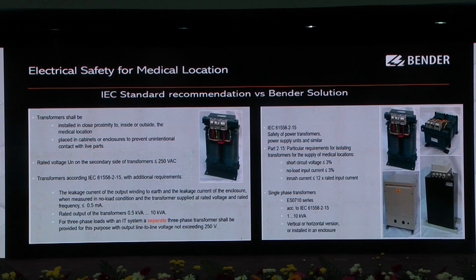So these are our isolation transformers, which we manufacture from 0.5 kVA to 10 kVA. It is as per standard. You can see IEC 61558-2-15, a standard for medical grade transformers. If you touch a live cable at the transformer output, you will not get a shock. Our noise level is also very low, short circuit protection is less than 3%, and no-load input current is less than 3%. Even inrush current is less than 12 times the rated input current.